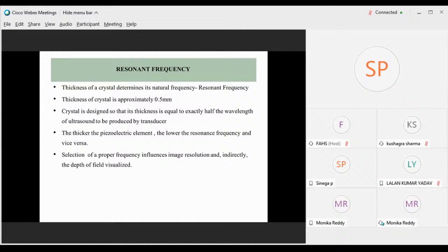So selection of proper frequency influences the image resolution, and indirectly the depth that will be visualized. The thickness of the crystal is responsible for both the frequency and the depth of tissue visualized. So transducer frequency is inversely proportional to the depth of penetration of the ultrasound signal into the body, and directly proportional to the image resolution. So increased frequency gives better image resolution, but it cannot reach the deeper structures.